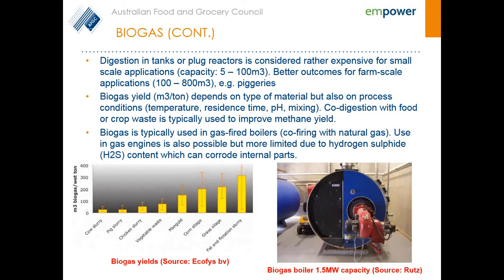In terms of end use, a typical application is using gas-fired boilers where you can co-fire biogas with natural gas. The co-firing ratio can depend on a number of things, mostly the burner design, which will have some limitations in terms of how much volume you can feed to the burner. Because biogas has a lower heating value compared to natural gas, it will require a larger volume to supply the same amount of energy.